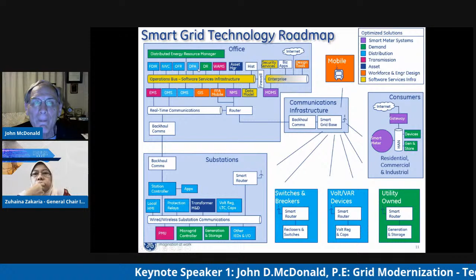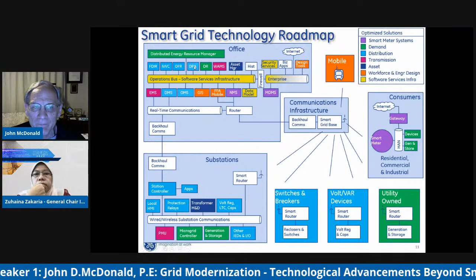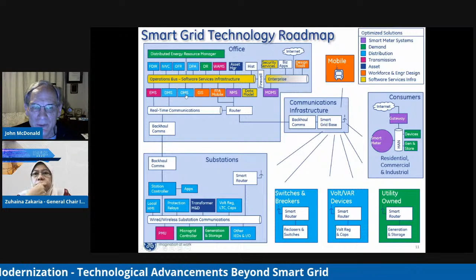In the upper left, these top four blue boxes are software applications on a DMS: fault detection, isolation and restoration, integrated VoltVAR control, optimal feeder reconfiguration used in restoration, and distribution power analysis, our 3-phase load flow program. Then we have the distribution management system and the outage management system.